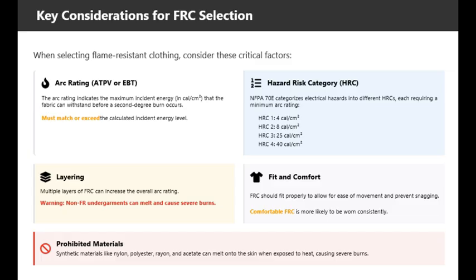Layering is another important consideration. Wearing multiple layers of FRC can increase the overall arc rating, but there's a critical warning here: non-FR undergarments can melt and cause severe burns. If you're layering, everything that touches your skin must be flame resistant.